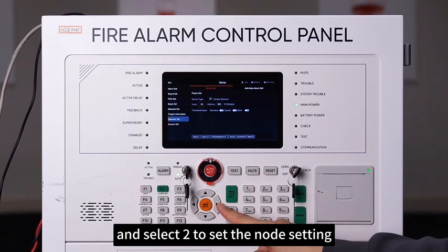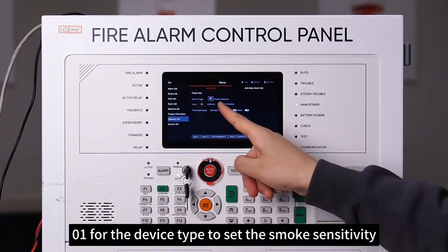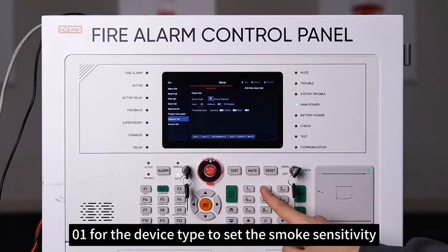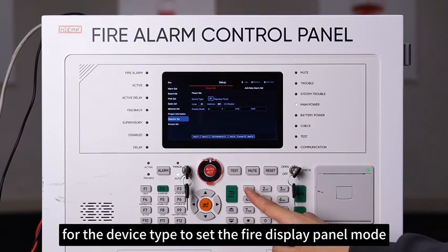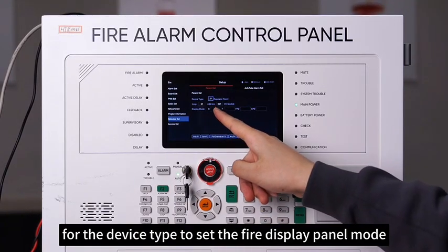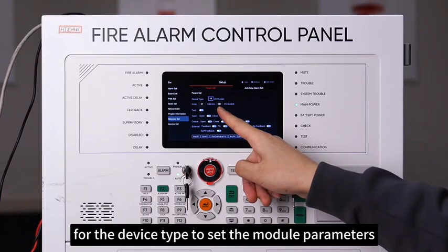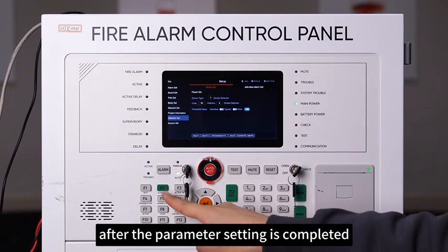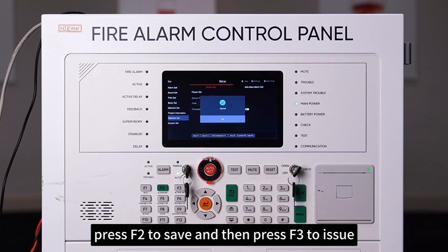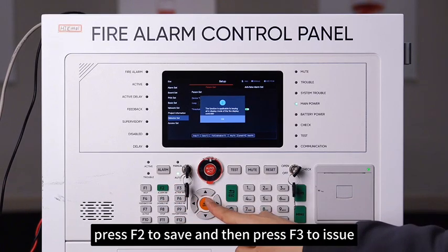the node setting. Enter 01 for the device type to set the smoke sensitivity. Enter 21 for the device type to set the fire display panel mode. Enter 16 for the device type to set the module parameters. After the parameter setting is completed, press F2 to save and then press F3 to issue.